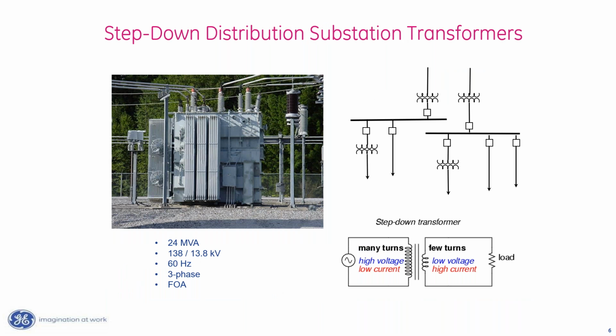Another broad category that we have is a step-down transformer. A step-down transformer is a transformer that we typically have at the other end of the transmission line. So this might be in an industrial facility. It could be at a distribution utility at their substation where they transform from high voltage that we're transmitting to medium voltage distribution. So this is something in the neighborhood of 161, 230, 500 kV down to a lower voltage winding of 12.47 kV or 25 kV, something in the neighborhood, some medium voltage.